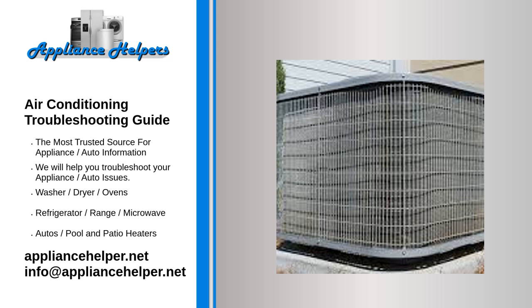It's getting hot in here, ironically, could mean a frozen evaporator coil. While embarking on your air conditioning troubleshooting mission, you should consider that your evaporator coil is the reason for warmer temperatures than you would like. This coil contains a refrigerant that absorbs heat. When airflow is diminished, a layer of ice can form on the evaporator coil. If this occurs, you could end up with warm air or no air from your air conditioner supply registers. The restricted airflow could be the result of dirty air filters, low refrigerant, or obstructed return air in your ductwork.